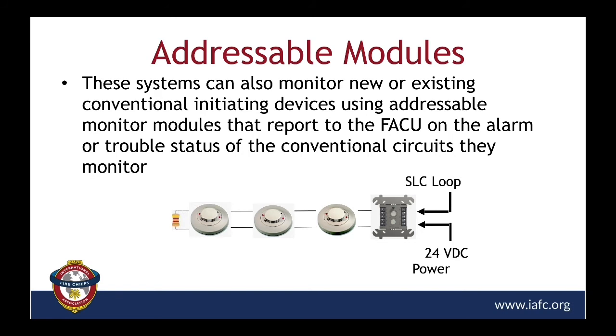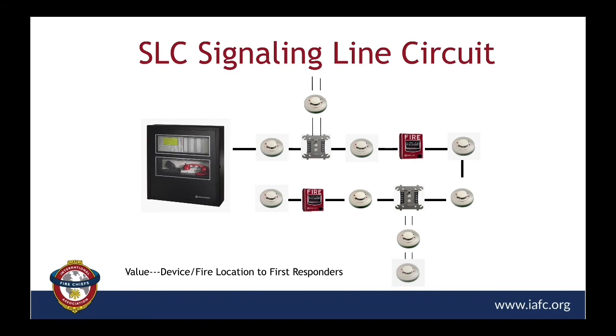Well, they have addressable modules, and you're going to see the module down here, this little stainless steel 4-inch by 4-inch device. These are usually located in a 1900 box and often have a white cover on them. Maybe they'll have some numbers like 20-04 on them. That's the address. You'll often see these next to the sprinkler water flow riser and the tamper switch area with the OS&Y valves.